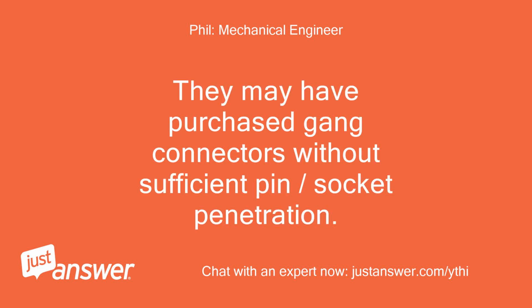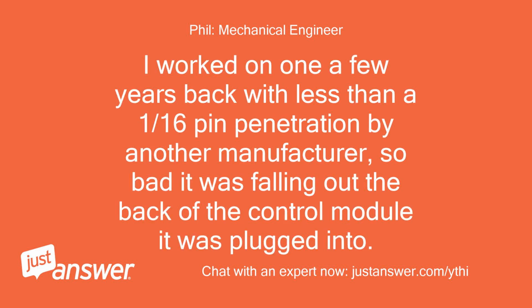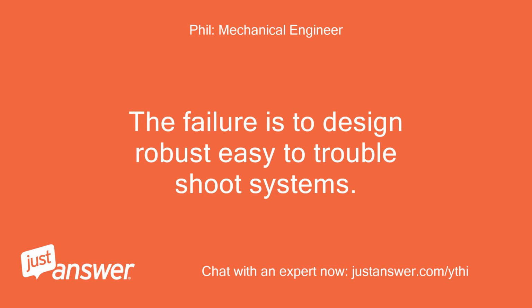They may have purchased gang connectors without sufficient pin and socket penetration. I worked on one a few years back with less than a 1/16 inch pin penetration by another manufacturer, so bad it was falling out the back of the control module it was plugged into. The failure is to design robust, easy to troubleshoot systems.